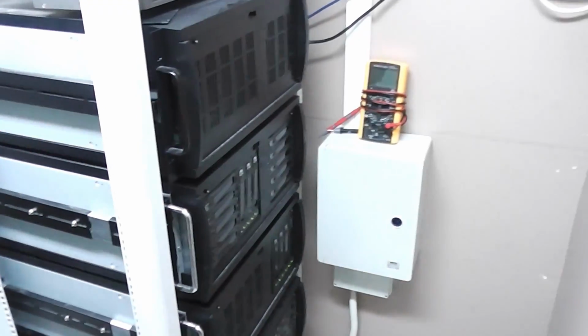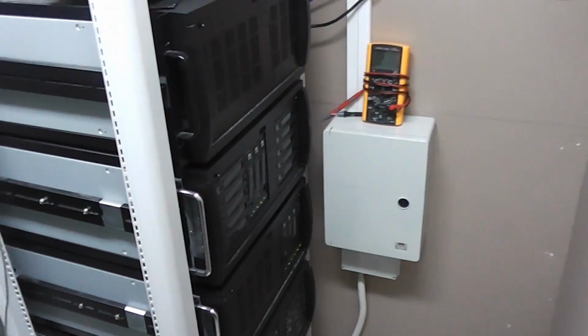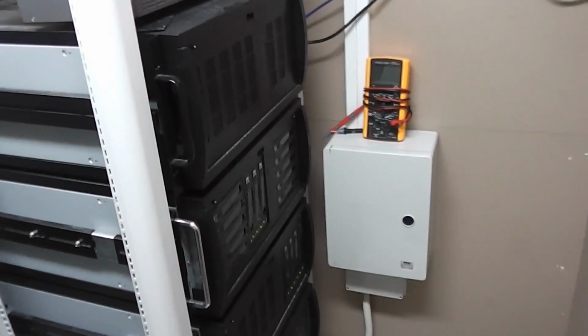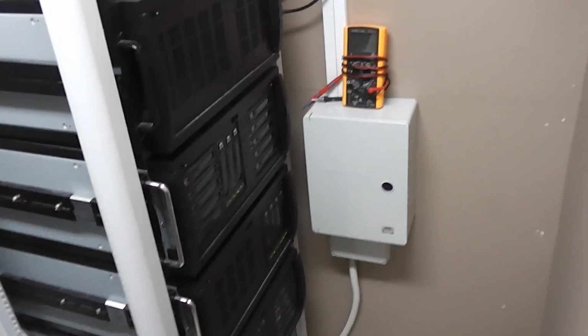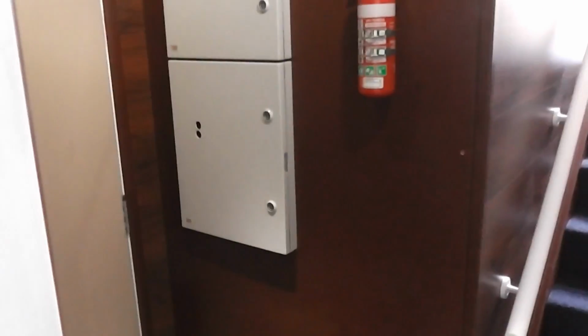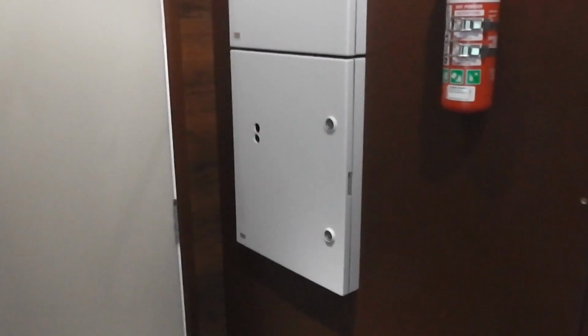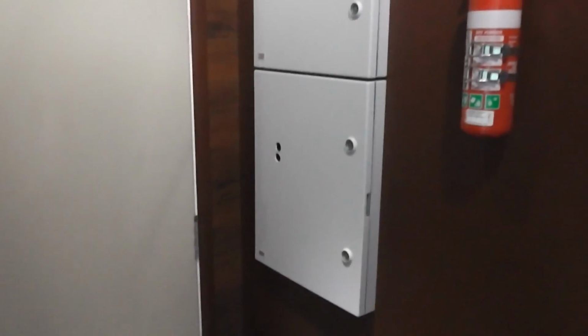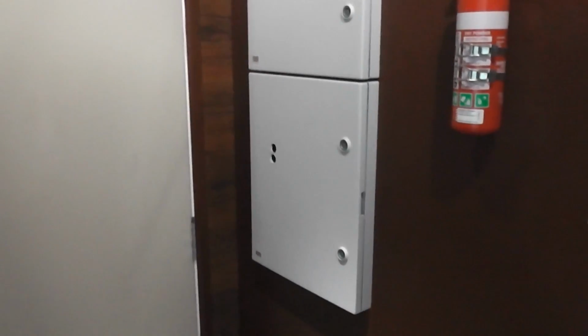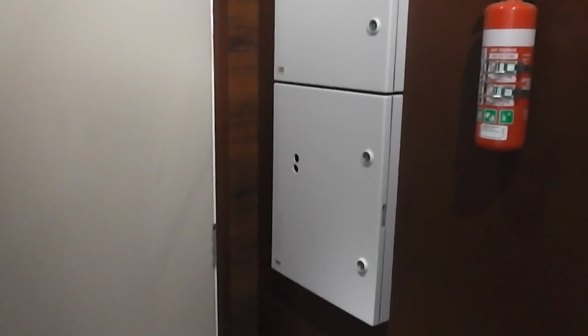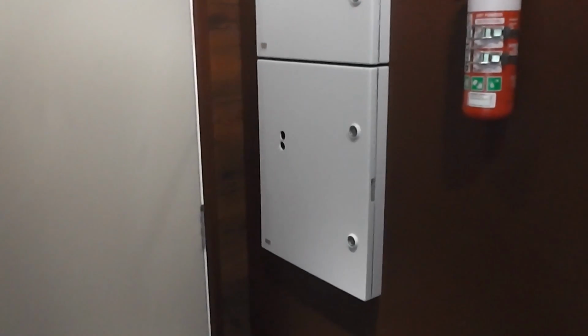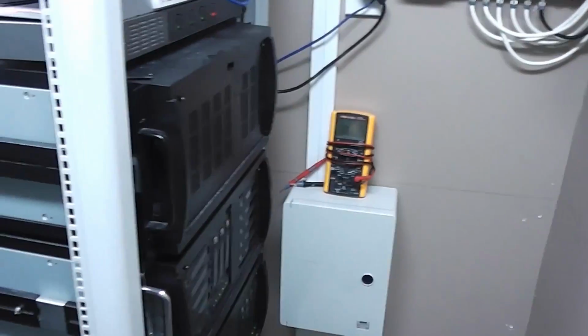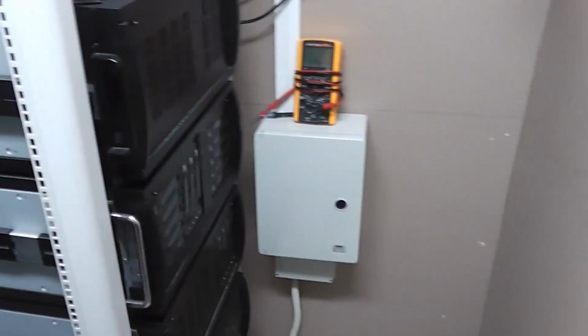It's a 16 amp single phase generator, so it can run all this stuff plus the air conditioner and the emergency lighting, with a bit of spare capacity, but that's all I'm using the baby generator for. The main generator is a 3-phase 32 amp per phase genset, so that's 96 amps in total. It can go a little higher, but it's fused at 32 amps per phase. So anyway, the baby generator is for running the server room.